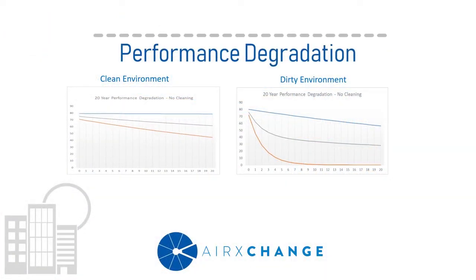So if an energy recovery component gets dirty, what's its relative impact on performance? In most modern buildings, you're going to have a gradual linear degradation that happens over time. Looking at the charts, you'll see three lines. The top blue line represents the device's ability to transfer heat. The bottom red line is the device's ability to transfer water vapor. And the middle line is the cumulative ability. As you can see from these curves, the device's ability to transfer water vapor decreases at a quicker rate than its ability to transfer heat.